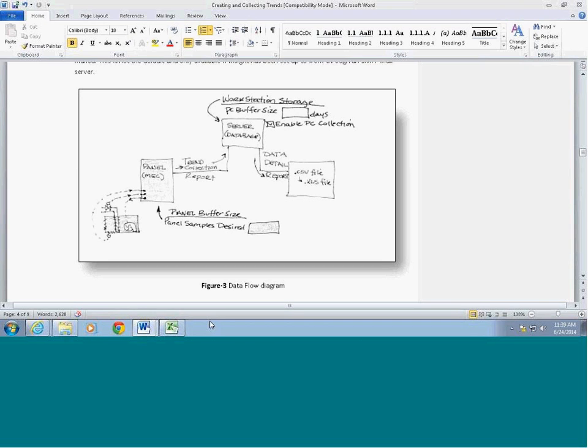This report is also challenged in that if it's too big, it'll fail. So in general, if you can limit to one file, again, it's easier to manage. Still recommend that ETC. But if you're doing more than 1,000 trends, you probably need to break it up into more than one. With 1,000 trends, we saw them start to crash. And that means that I believe you didn't get any of the trends, if I'm not mistaken.